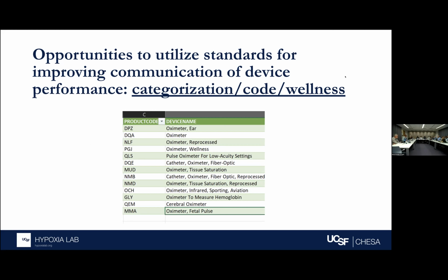So if you go to the FDA database, you look at a regulation or a particular product code, that product code regulation would have a definition, which regulation, and any pertinent standards that are used. And so if you look at DQA, you'll see all the biocompatibility standards, which are like ISO 10993, and you'll see the one that the committee here is discussing, the 80601-2-61, right? Those are the ones where a company comes in, they will declare that they conform to these standards because they're recommended by the agency. And those standards, when you follow them and you adhere to them, you would require the desaturation studies.